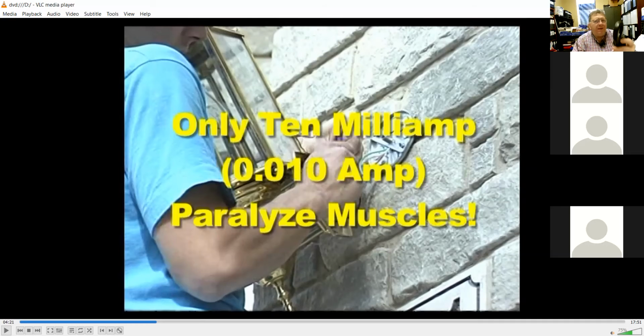Now, normally, when you're reading amps, you don't read but one wire. When you start using the meter to check volts and amps in the shop on your labs, when you check amps, you're going to run one wire through that current coil, and the meter's going to tell you how many amps is on that one wire. Now, here's what happens when you put 2 wires through a current pickup. If I put 2 wires through the current pickup coil, the meter is going to read the difference between the two.